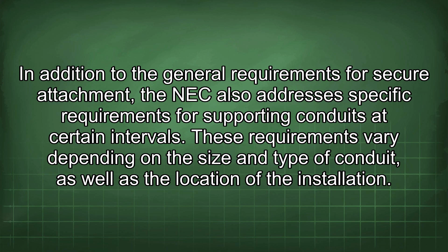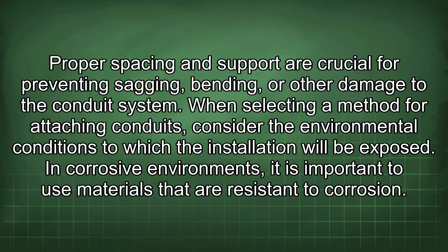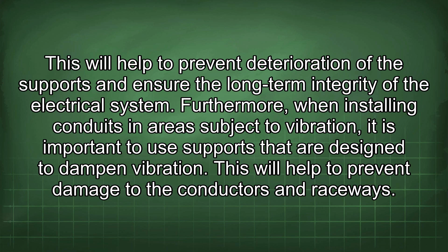When selecting a method for attaching conduits, consider the environmental conditions to which the installation will be exposed. In corrosive environments, it is important to use materials that are resistant to corrosion. This will help to prevent deterioration of the supports and ensure the long-term integrity of the electrical system. Furthermore, when installing conduits in areas subject to vibration, it is important to use supports that are designed to dampen vibration. This will help to prevent damage to the conductors and raceways.